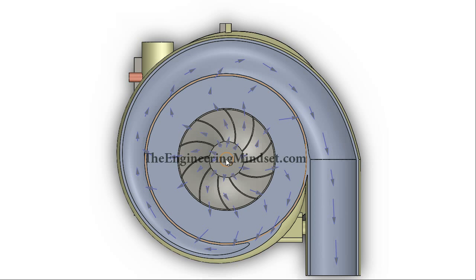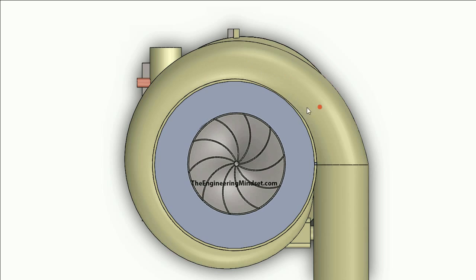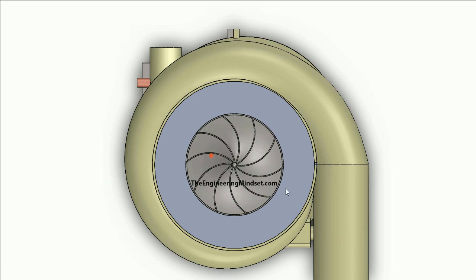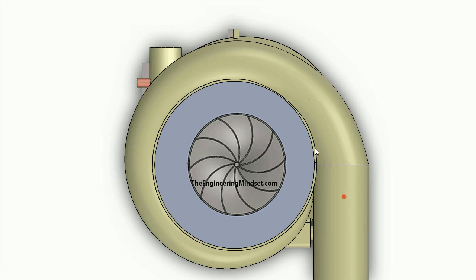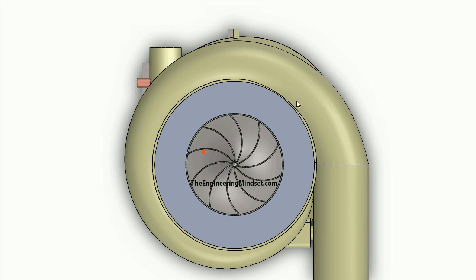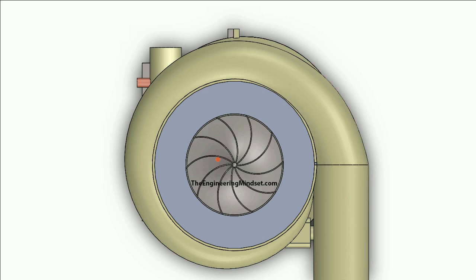The refrigerant flies in, and as it's flung off this compressor, it travels in all directions, collecting up in the volute and going off into the condenser. You can see that in this animation here — the particle flows off, the impeller rotates and flings it outward, collecting in the volute and building up in pressure, then making its way down to the condenser.